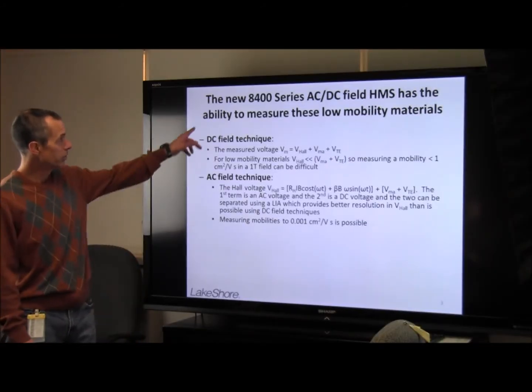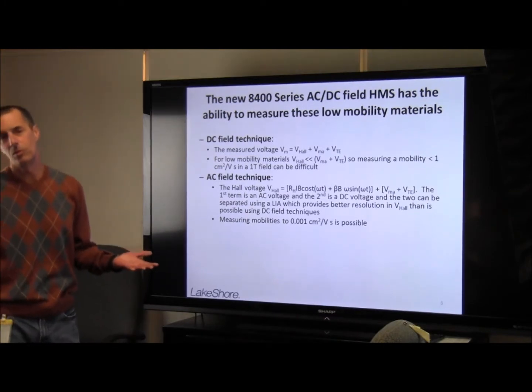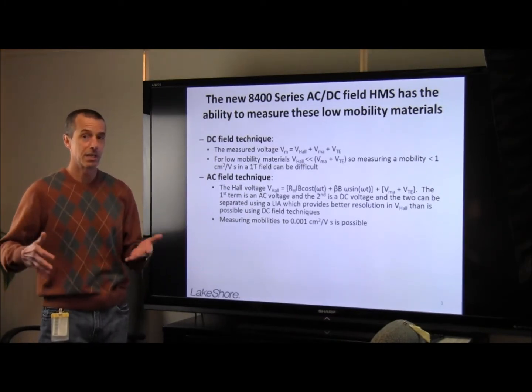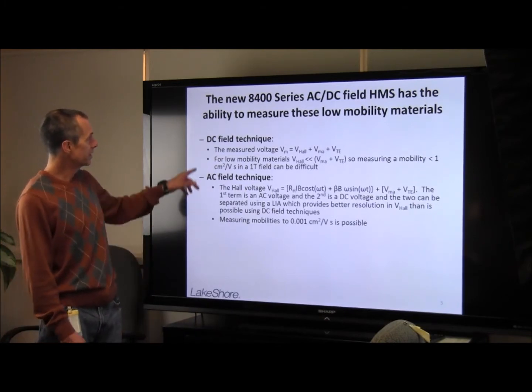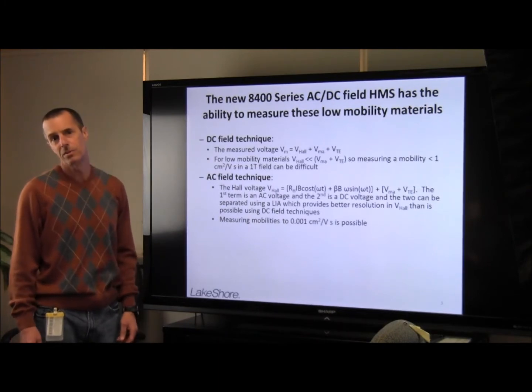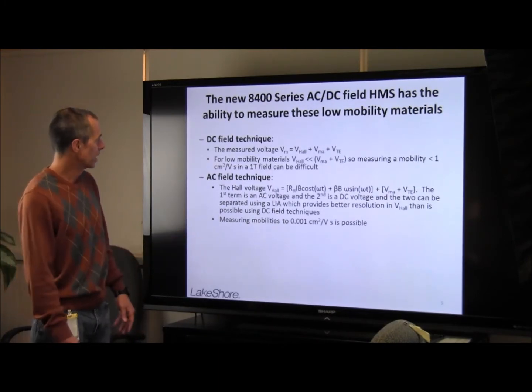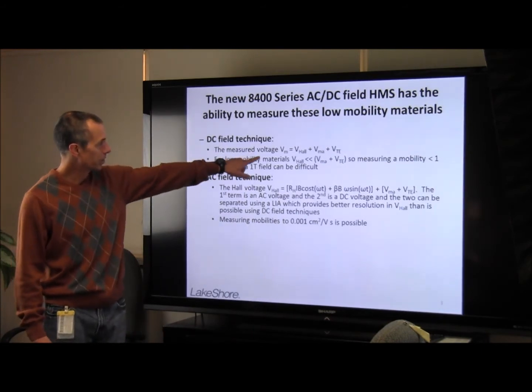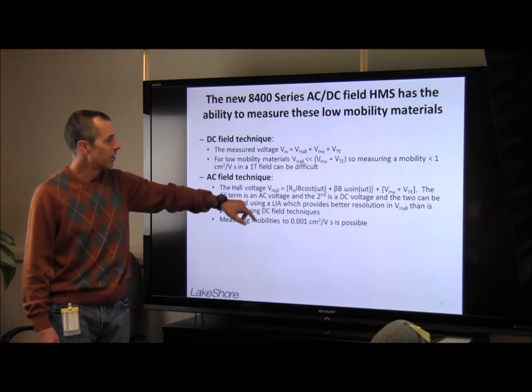Lakeshore's new 8400 series Hall Effect measurement systems are capable of doing both DC field measurements and a novel AC field technique. In a DC field technique, it can be very difficult to measure very low mobility. The voltage that you measure, V sub M, is equal to the Hall voltage — this is what you want — but there are also offset voltages present.